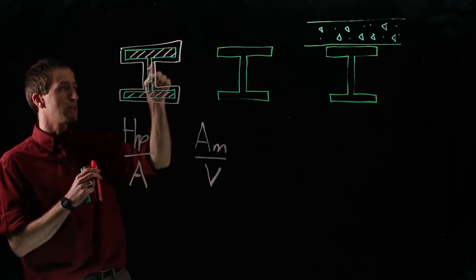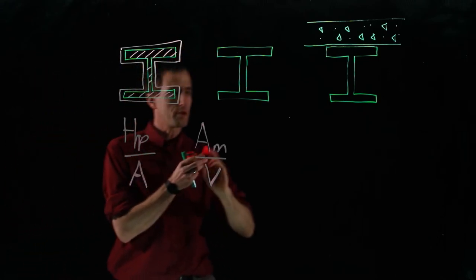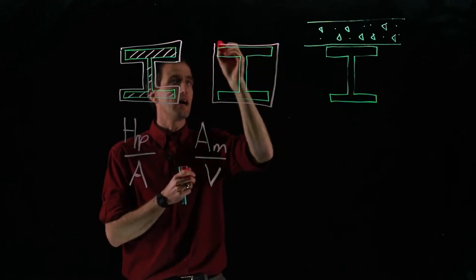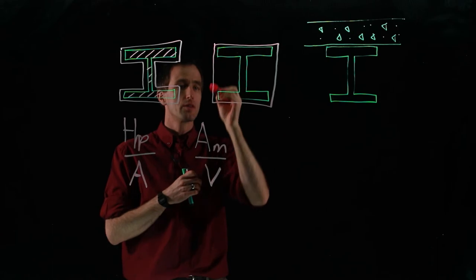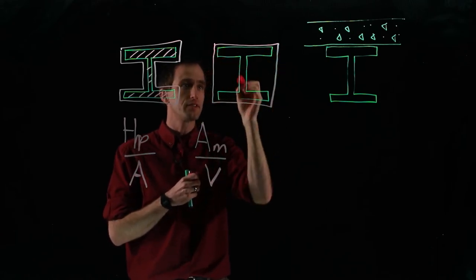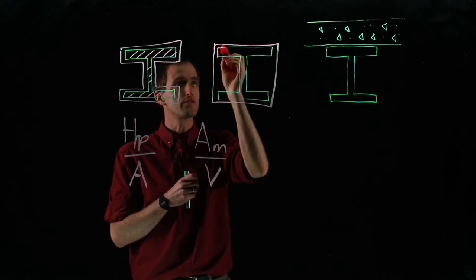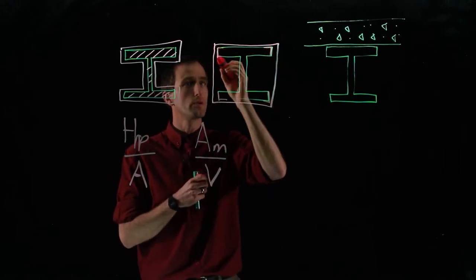Either we can do contour passive protection as per the pink line, or we could do a box passive protection all the way around it. Now the amount of energy entering the sample has reduced because the perimeter is smaller. We don't have the full contour inside, but we take the dimensions right on the edge of the steel all around, so we use the contour all the way around.